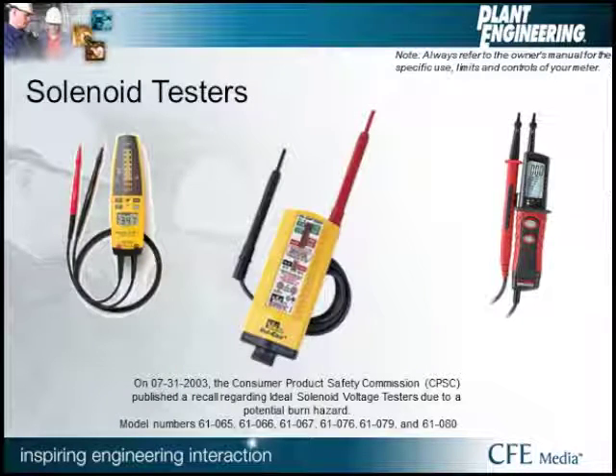We have here solenoid meters, or what some people call wiggies, and these are used for both voltage testing and continuity testing. I want to point out that this image we have in the front is an Ideal solenoid tester, and it was the subject of a Consumer Product Safety Commission recall. So if you have this type of meter, or any type of meter, be sure to check periodically to make sure there's no recall.